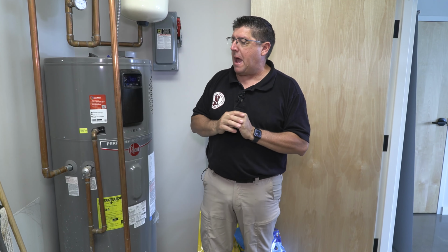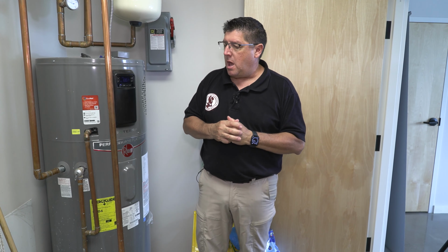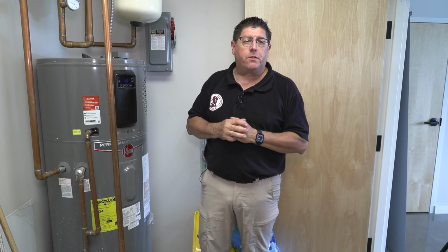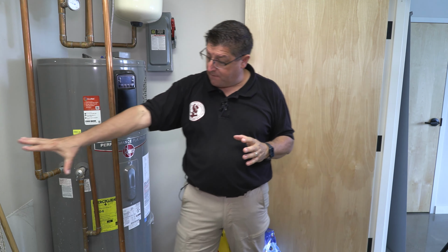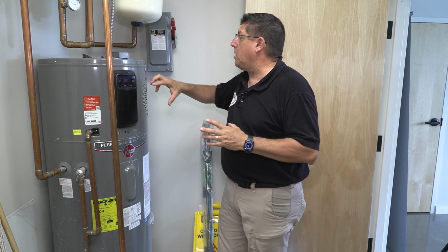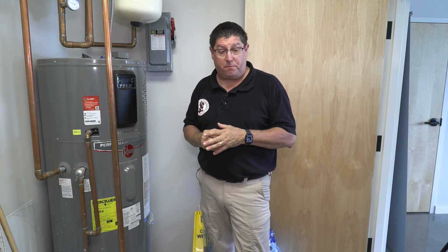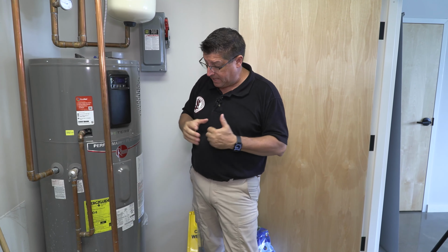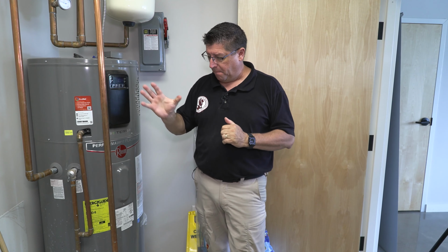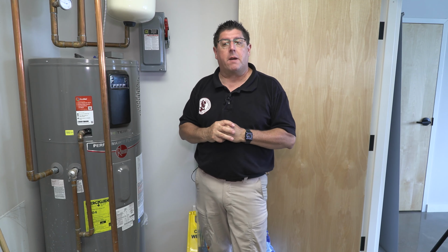We'll find similar vacuum breakers behind urinals in men's bathrooms and other systems. Sometimes there could be a vacuum breaker hanging out of the wall in a random location. That would be suitable and just fine for this apparatus. But in this case, I do not see a vacuum breaker at all. This would be an issue that I would want to flag for my clients.